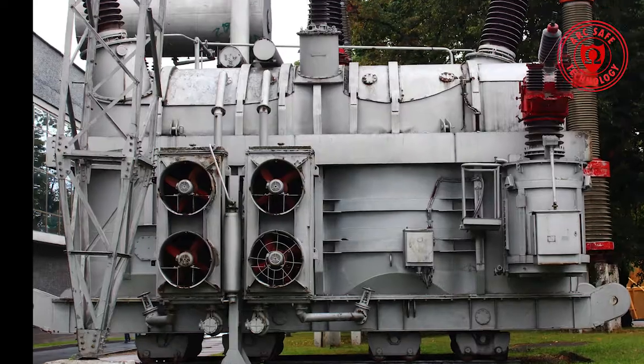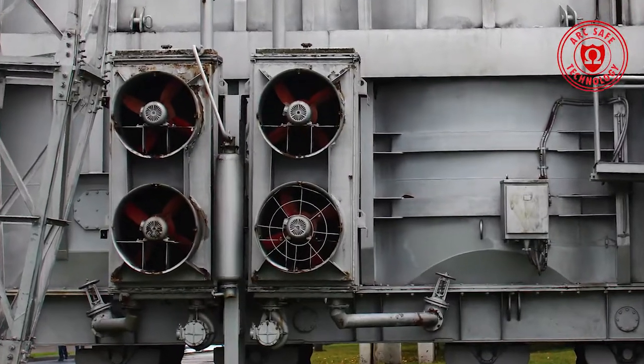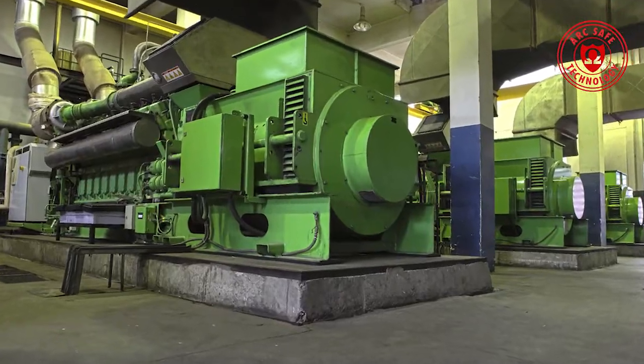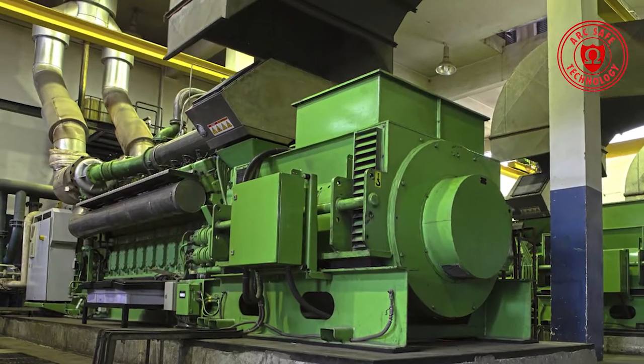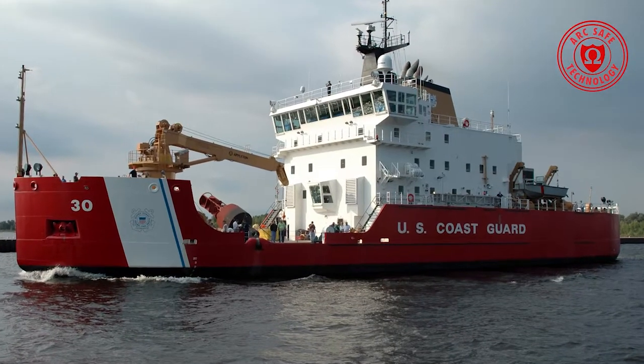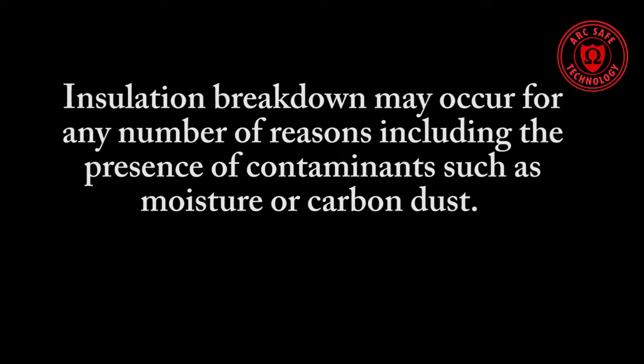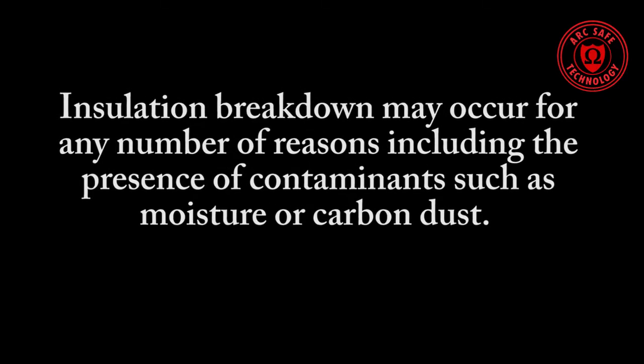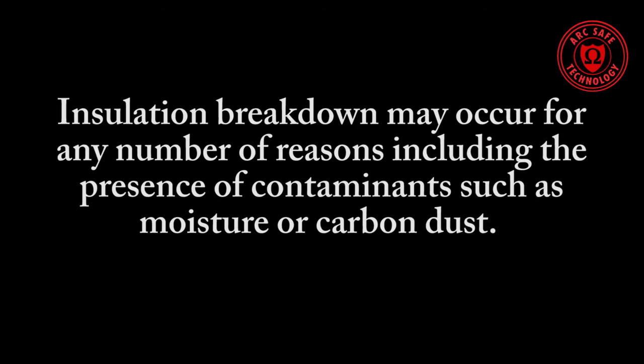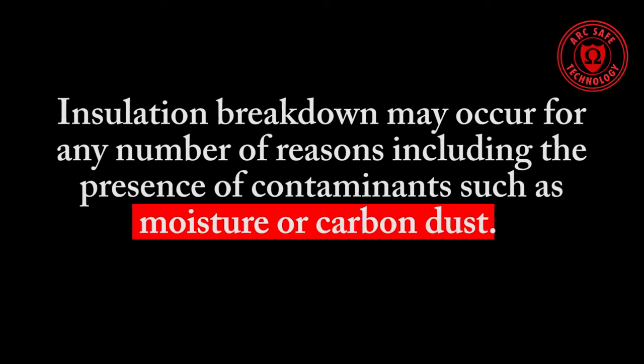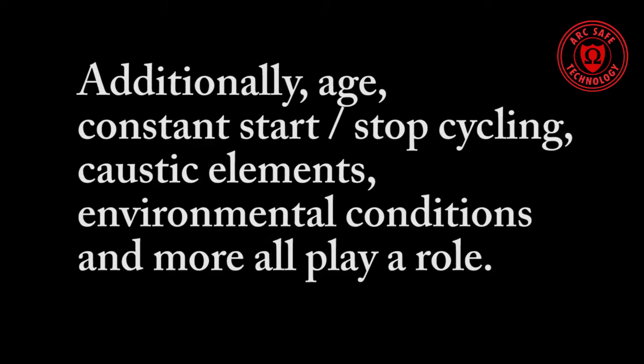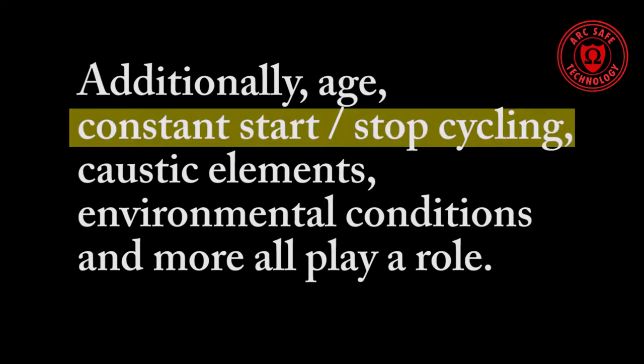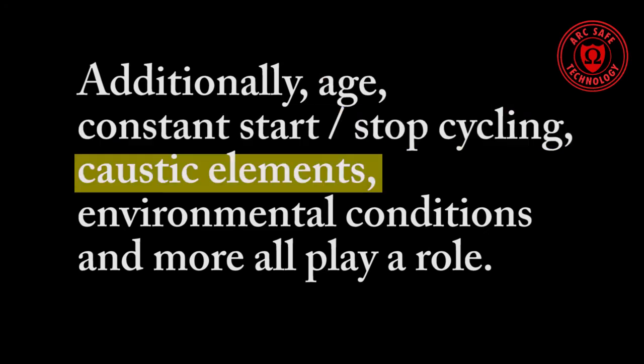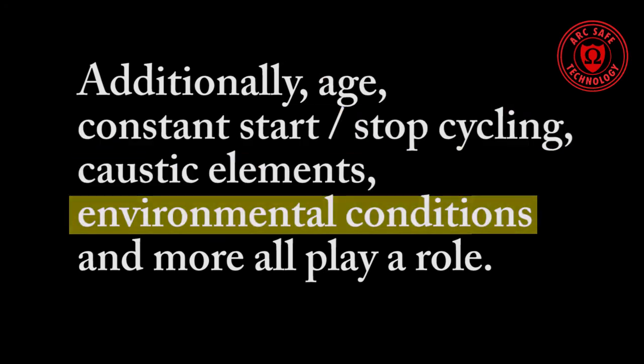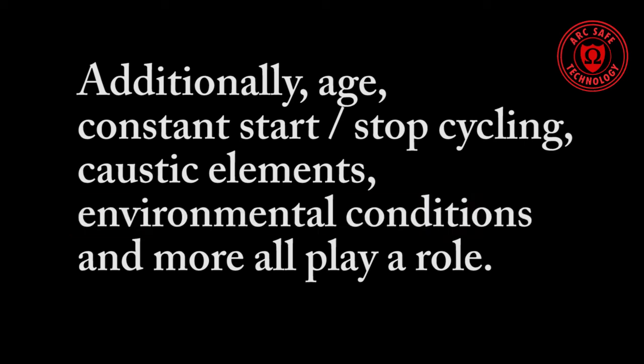The vast majority of electric motors and generators fail at startup due to insulation breakdown, allowing current to find an unintended path to ground. Insulation breakdown may occur for any number of reasons, including the presence of contaminants such as moisture or carbon dust. Additionally, age, constant start-stop cycling, caustic elements, environmental conditions, and more all play a role.